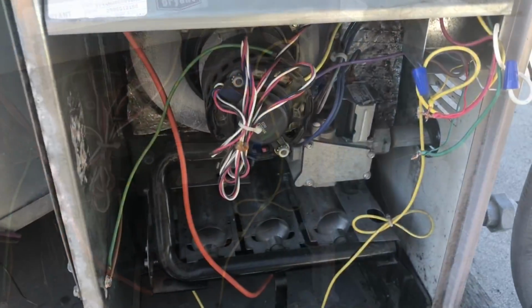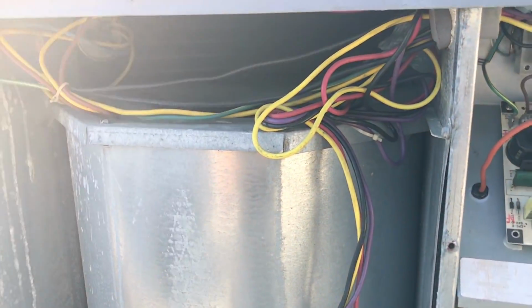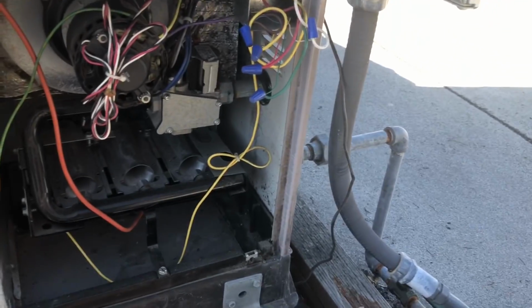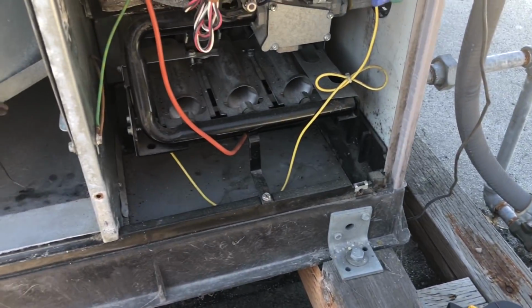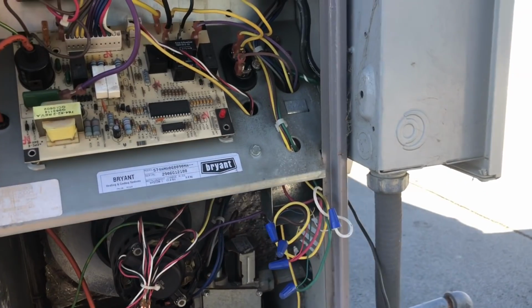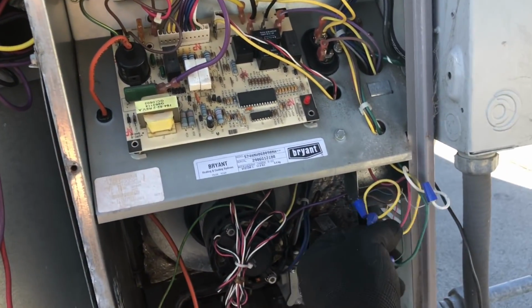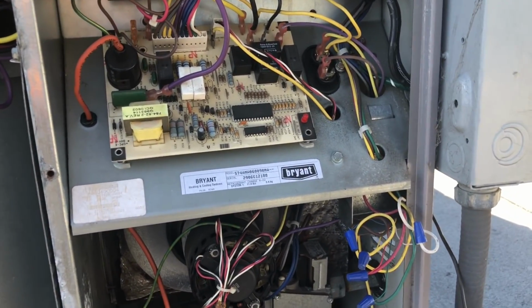So we did a quick check. Let's get a quick little jumper out, make sure everything's running. I'm going to jump downstairs and see what's up with that voltage coming down this thermostat wire. I know on the red I got 24 volts, so let's go check it.